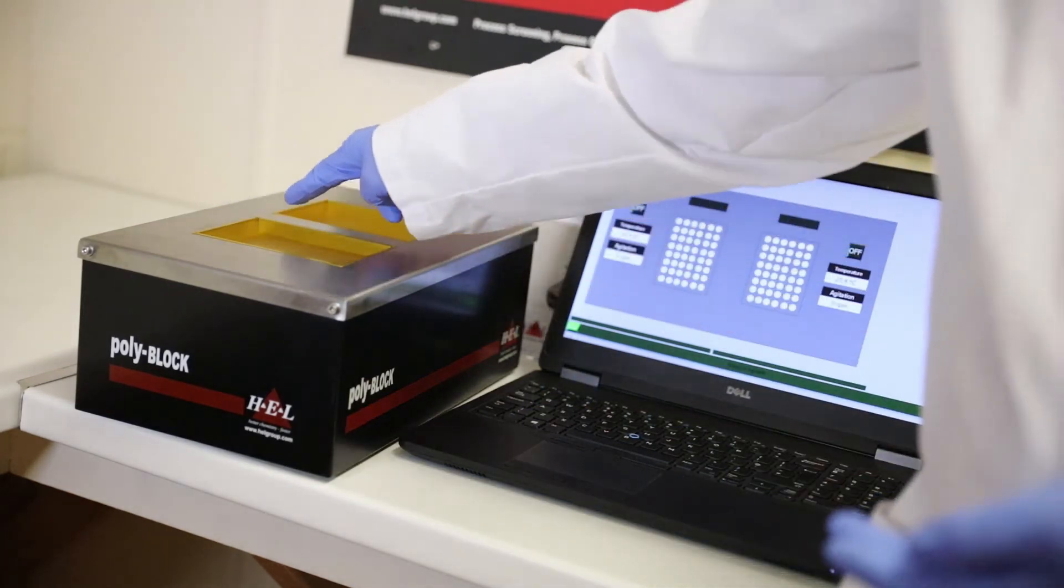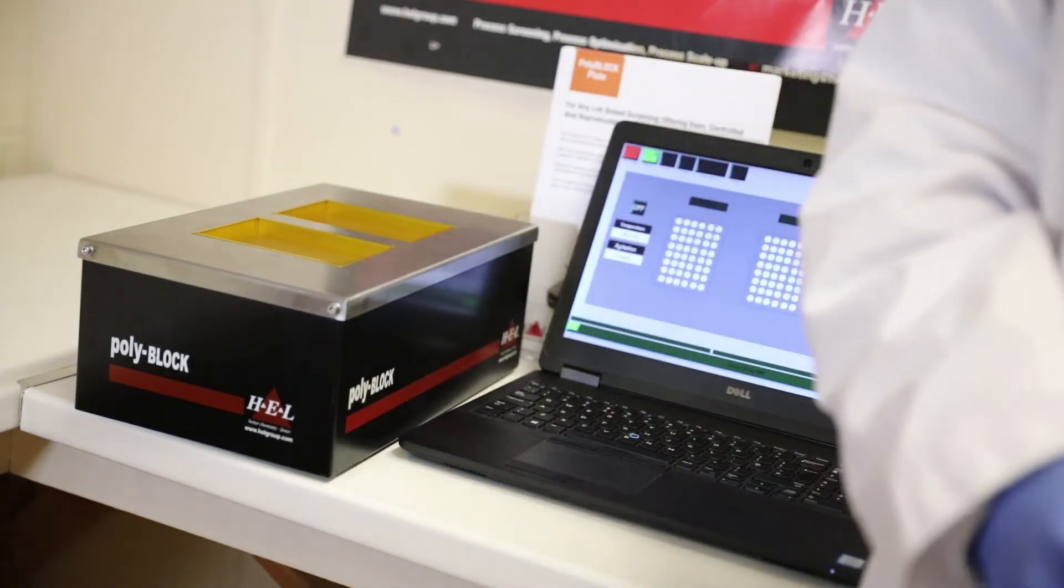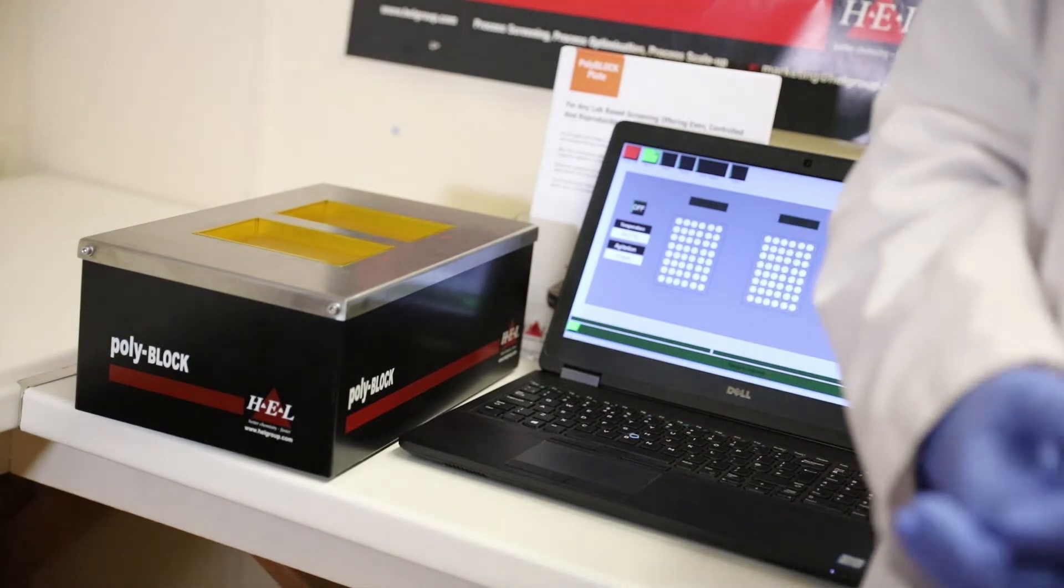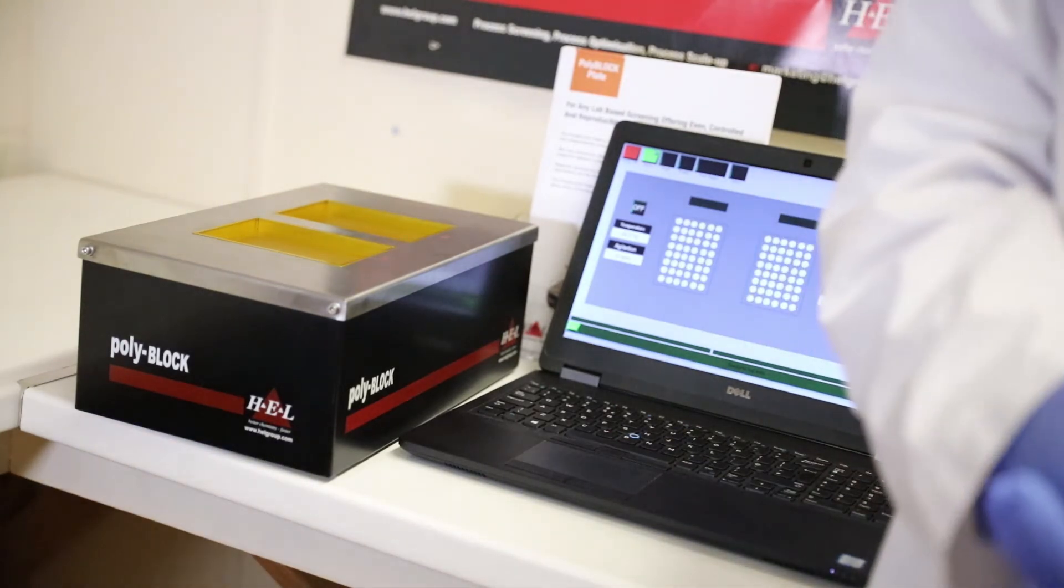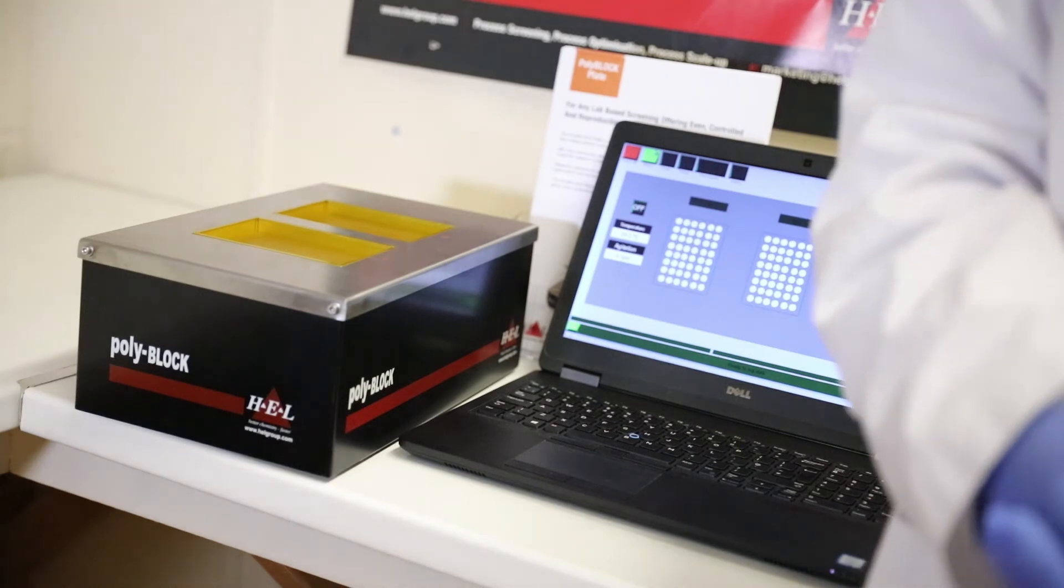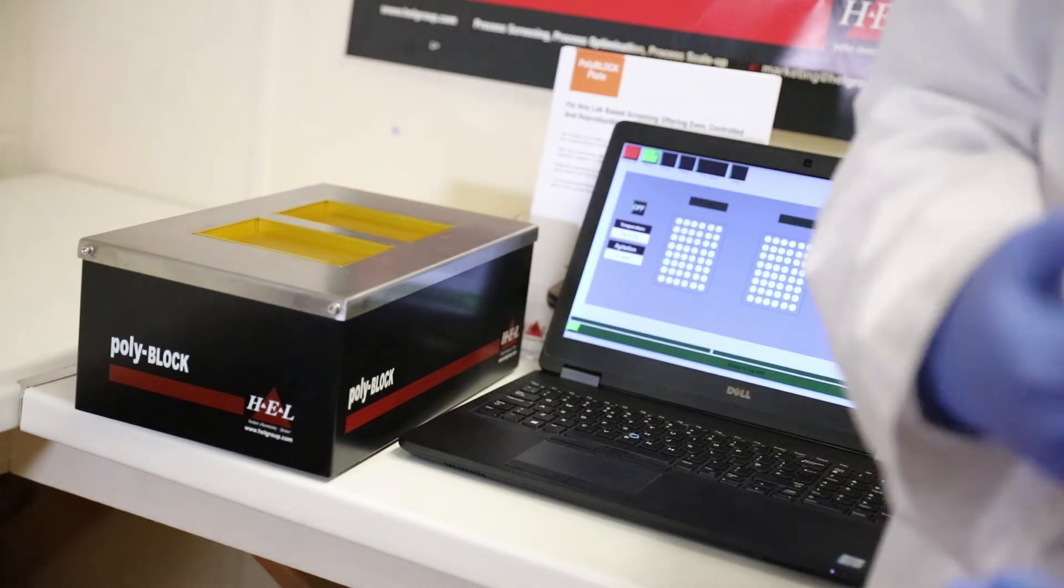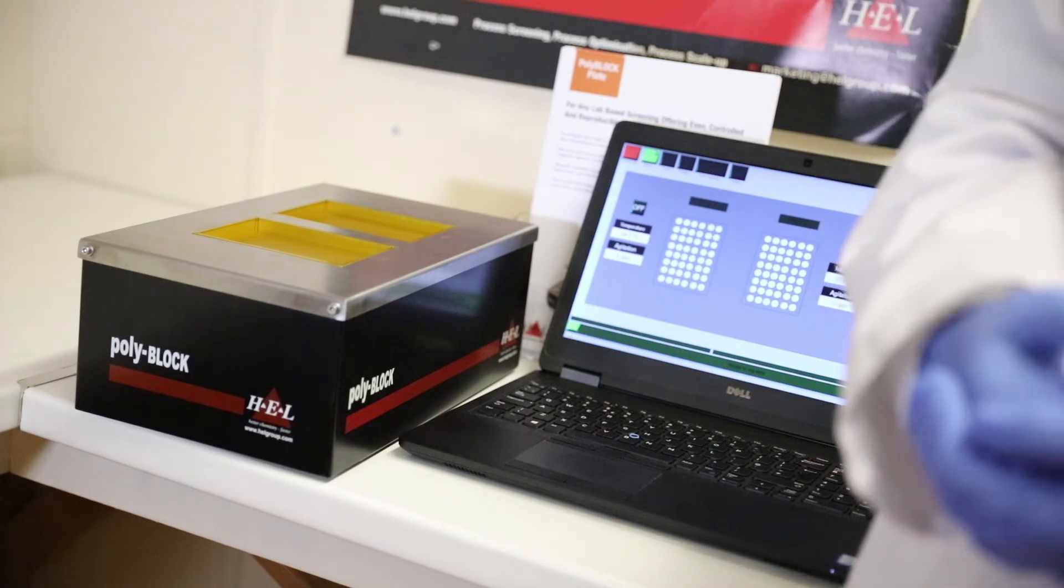Underneath each individual zone here are a number of magnetic stirrers. These have been precision positioned in order to give even magnetic stirring across a complete plate. So you get stirring in every single well of the plate.